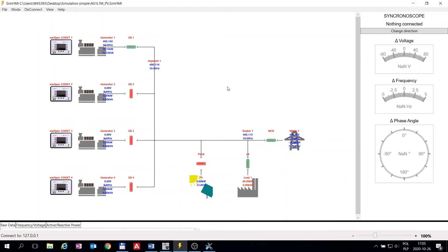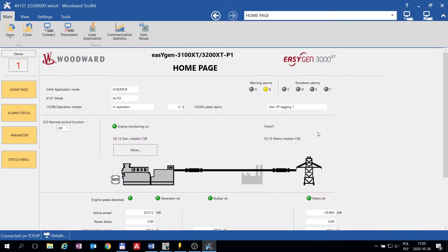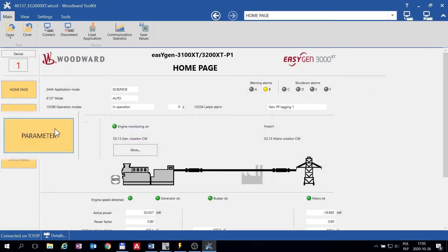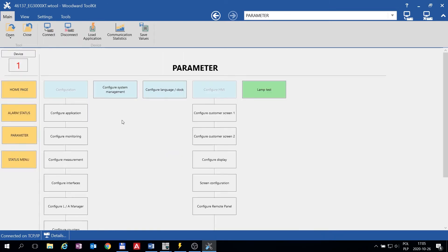Here we have our Simulation tool. You can see right now I have one generator connected. I have some load connected here, and we are parallel to mains. EasyGen is sharing the load with mains. Here we are connected to this generator with Toolkit. Let us configure a Flexible Limit alarm when we are exporting power to the grid.